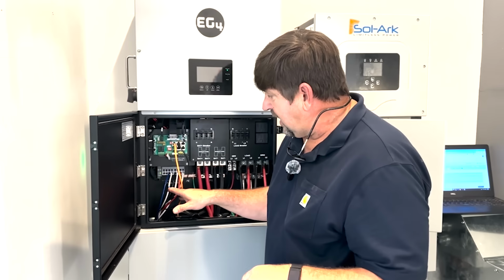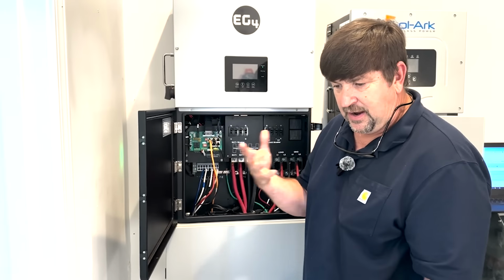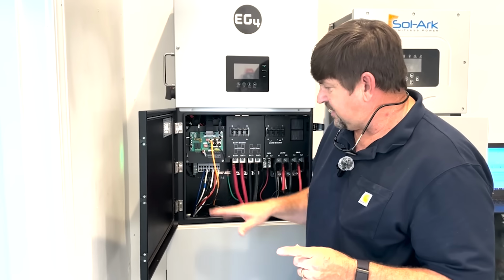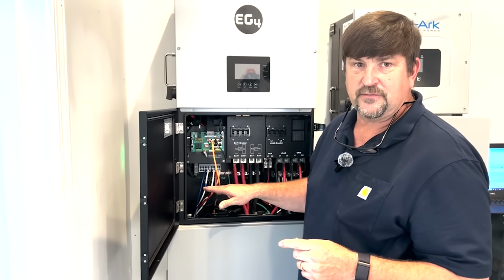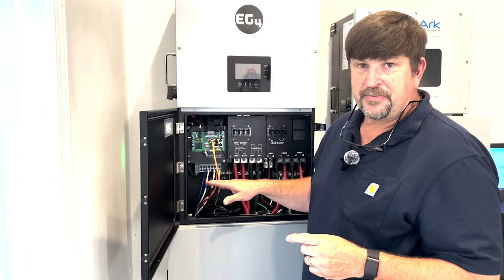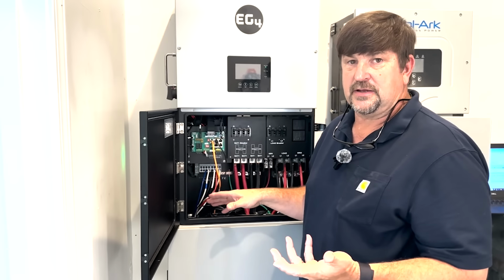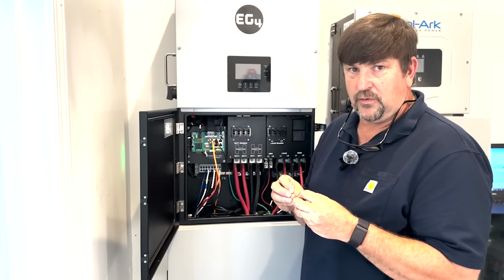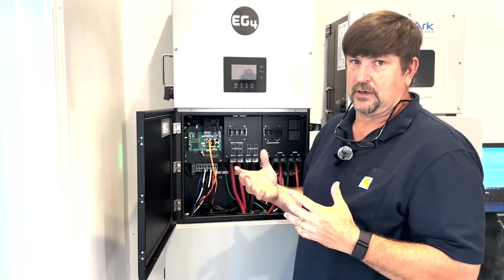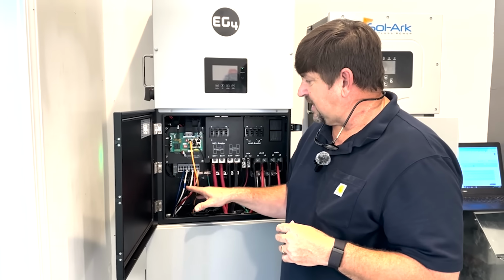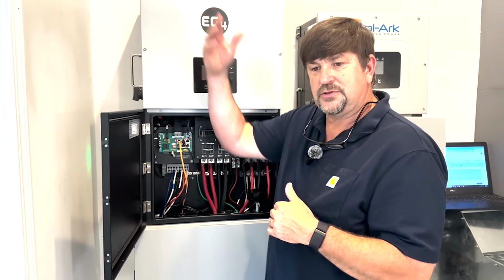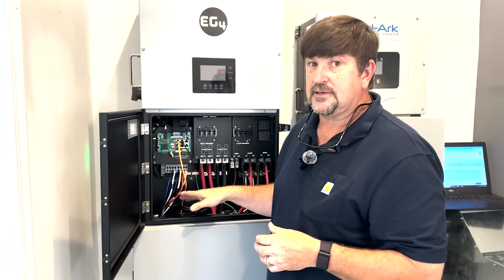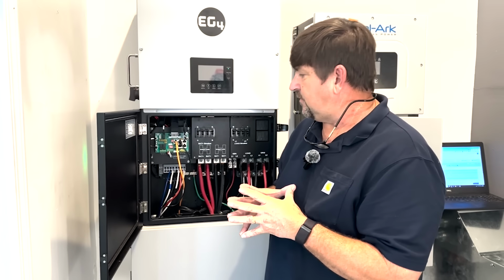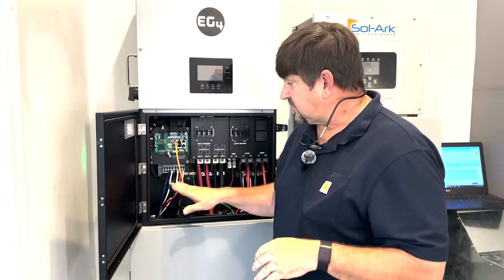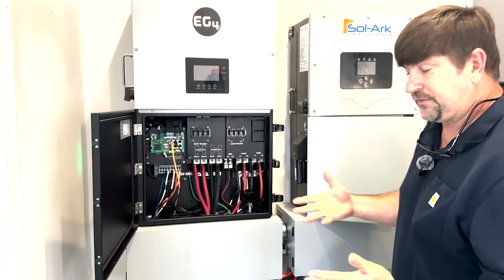With 4 strings and the panels I'm dealing with, even though the manual says the voltages can be different, we're finding that's not truly the case. They need to be similar voltage strings for the inverter to actually work. There have been tests running different voltages for shade mitigation, but it doesn't work. They need to be similar voltages. That's a limitation, so 4 strings at a higher voltage.